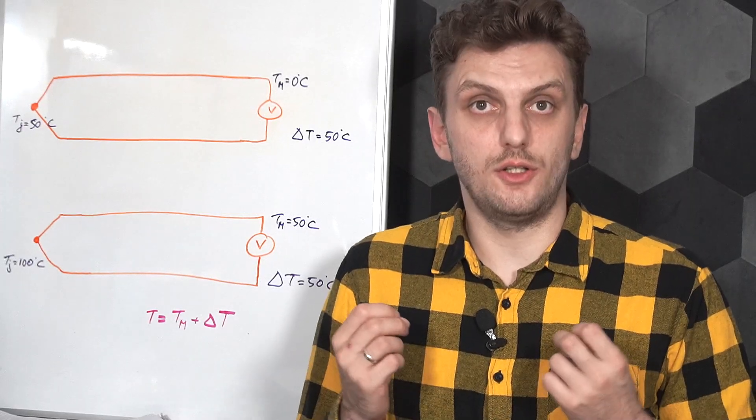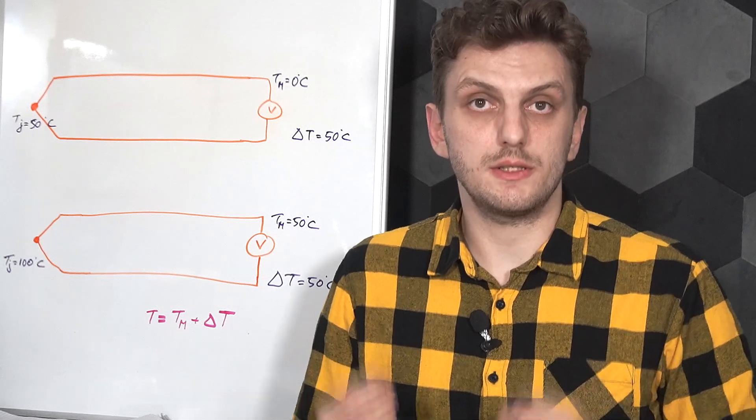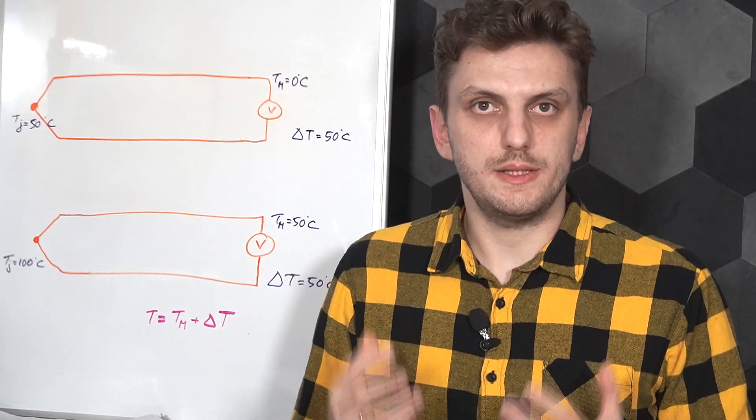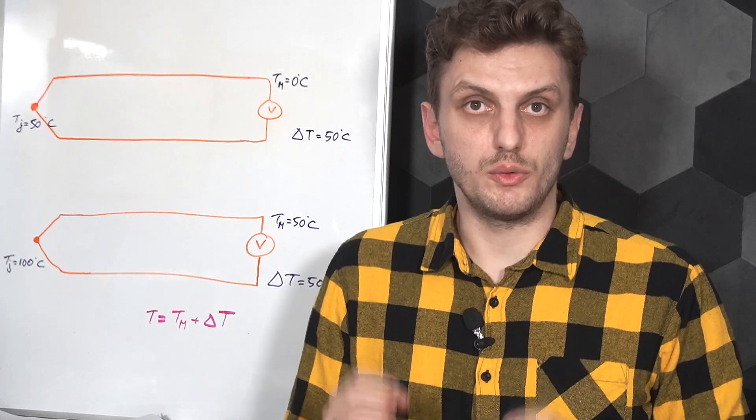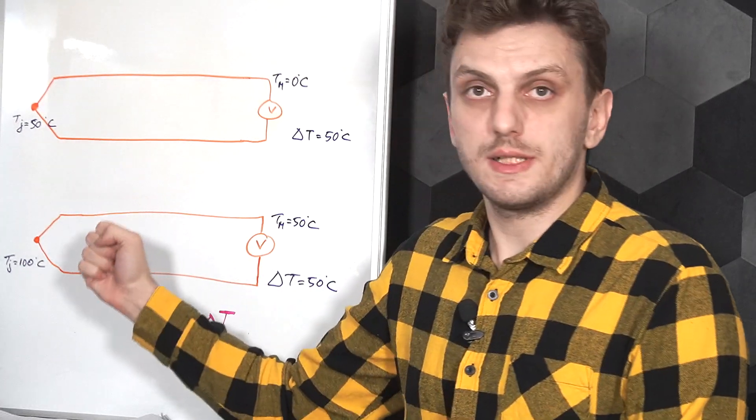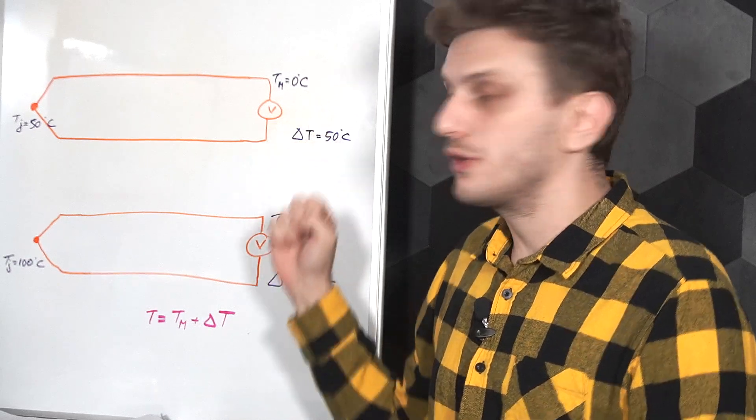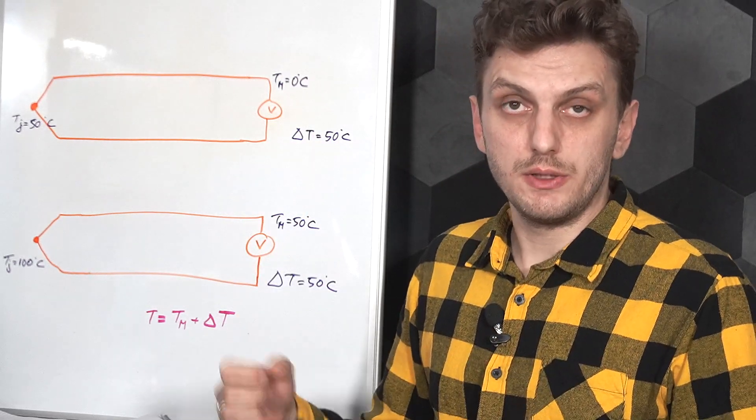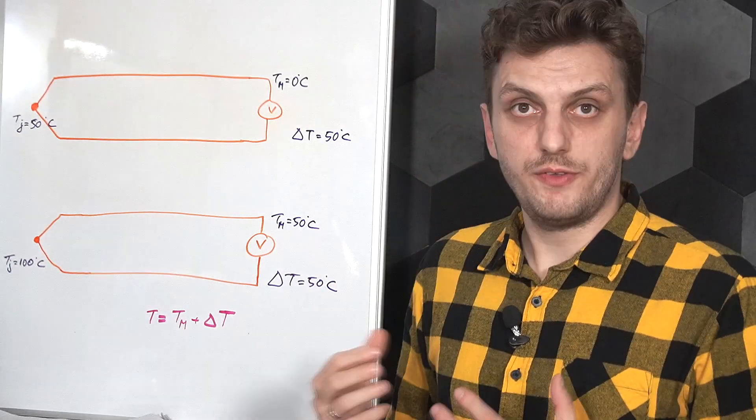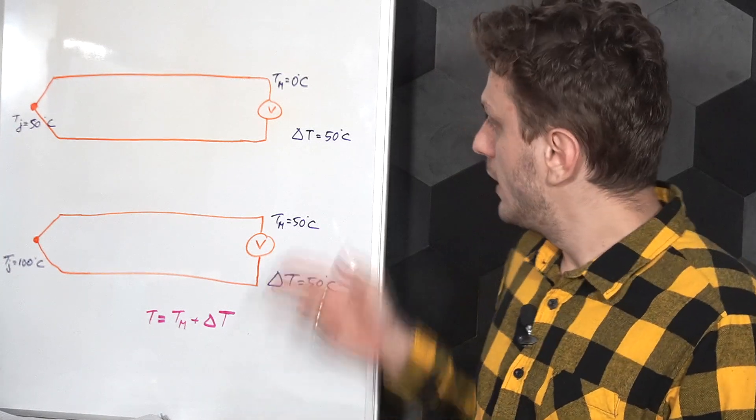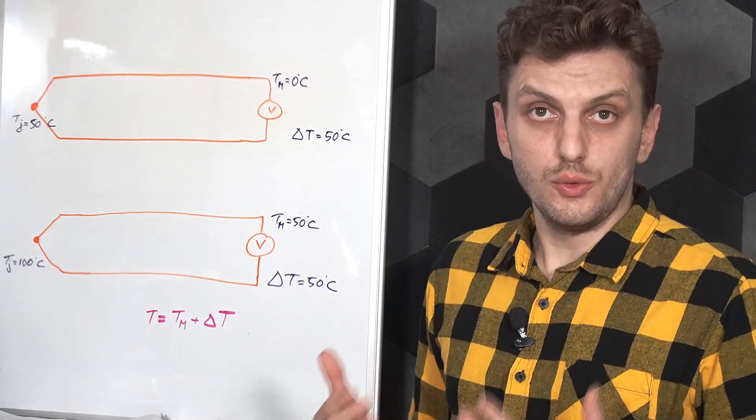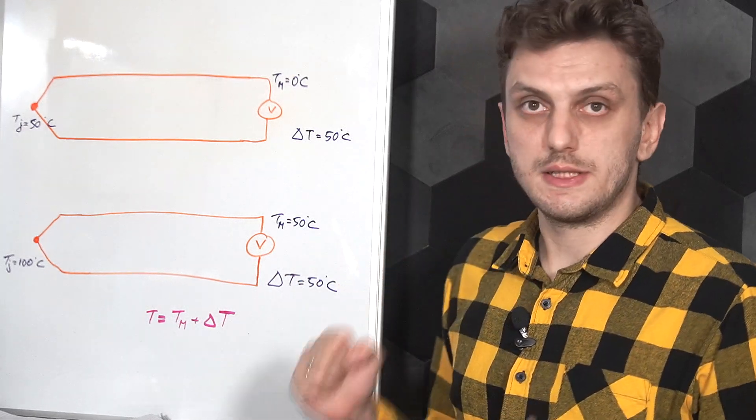First of all is the operating principle. A thermocouple is a relative temperature measurement method, not an absolute one like the ones we looked at previously. This means that a thermocouple will give you a voltage proportional to the temperature difference between its hot and cold ends. If we have a thermocouple whose junction is at 50 degrees Celsius, and the measurement equipment is at 0 degrees Celsius, and we have another thermocouple made from the same materials, where the junction is at 100 degrees Celsius and the meter at 50 degrees Celsius, in both cases the temperature difference between hot and cold ends is the same, 50 degrees. So both of these setups will give us the same voltage value.